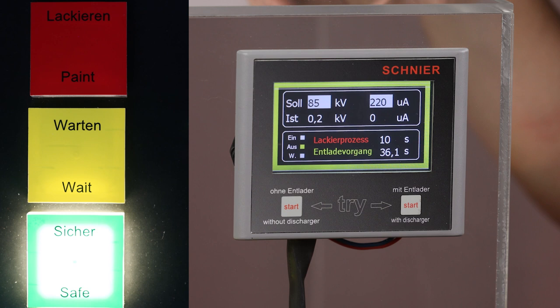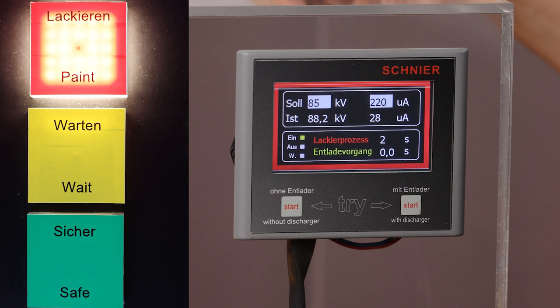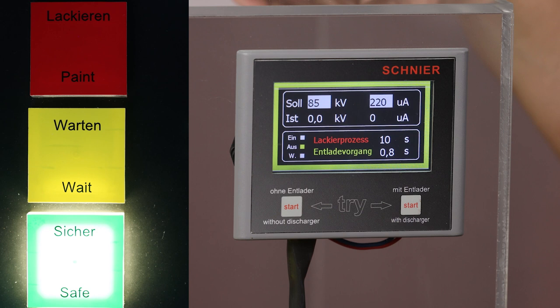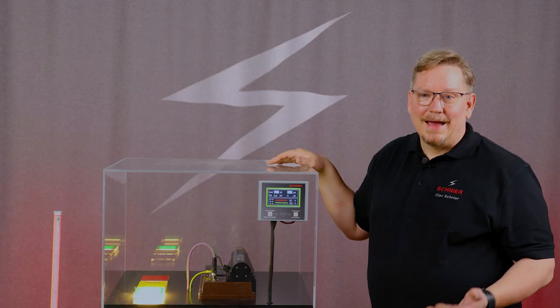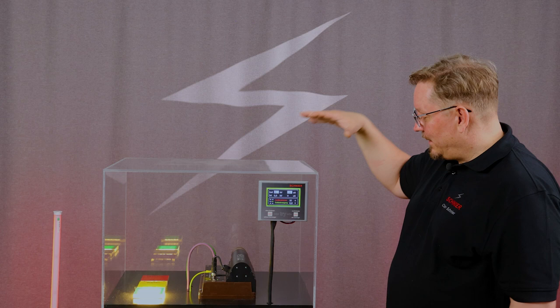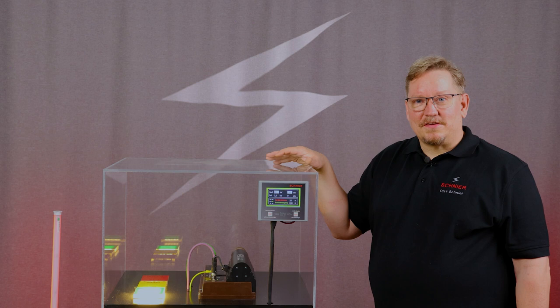If we now do the same with the discharger, the 85 kV is applied again. We have switched on the high voltage for 10 seconds. Switch off and we are immediately green. So, here you can see very impressively when you need the discharger. You always need it when time plays a role after switching off.